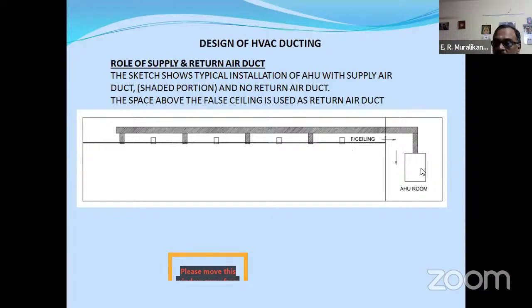What happens in summer? People will say the AC is not effective. The AMC fellow comes, cleans the filters, and goes. By the time summer is over, the situation is back to normal. Peak demand is always a headache. One more issue is that in the rainy season, plenty of condensation will happen in the space above the false ceiling. This condensation will damage the false ceiling and also promote fungal growth, especially in clean rooms and hospitals, where fungal growth is not a good thing. So these are the various things.